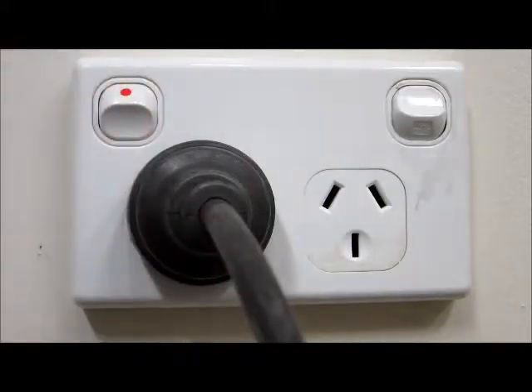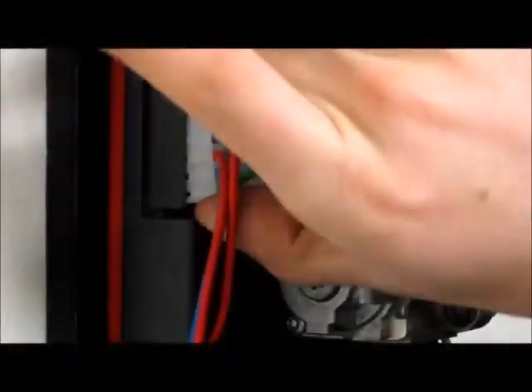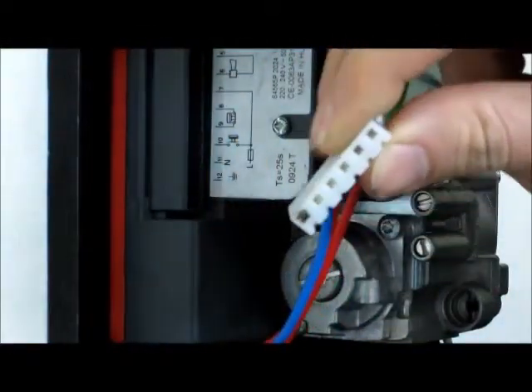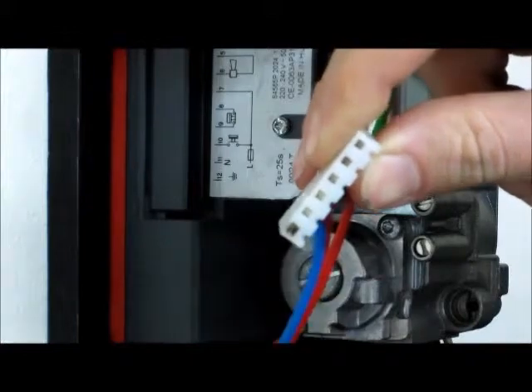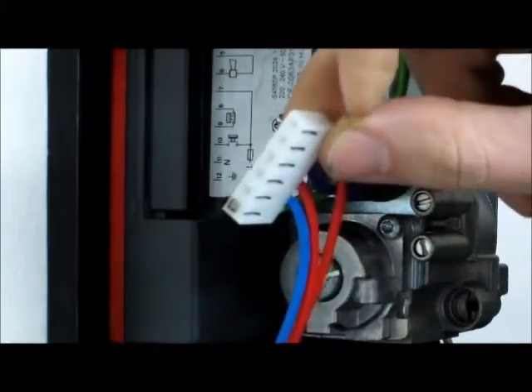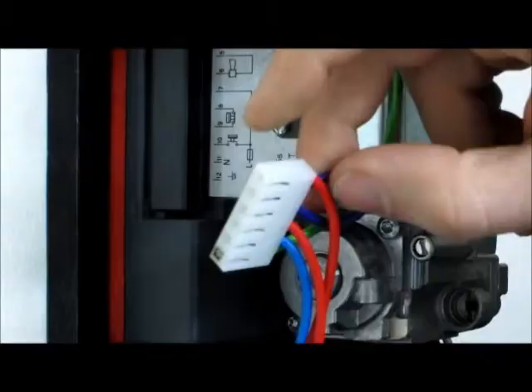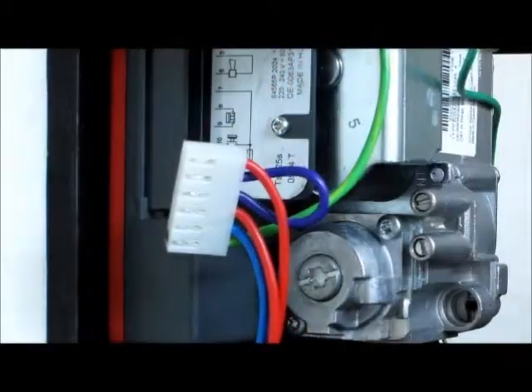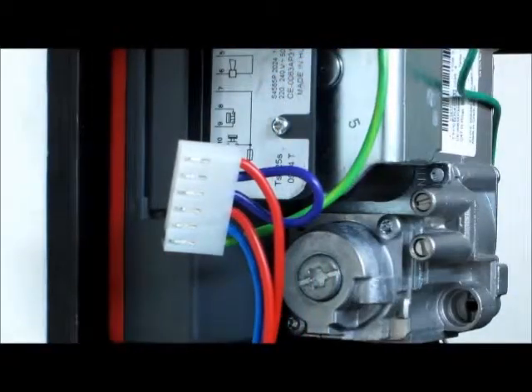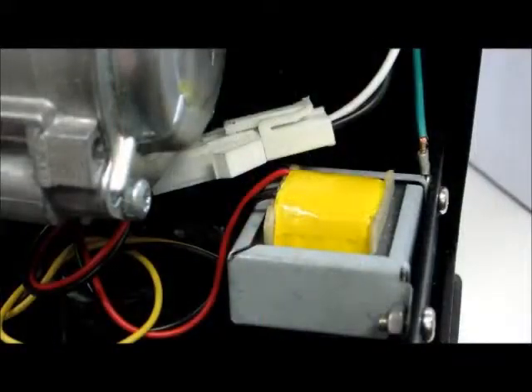Power up the unit, and if there is still no audible ignition signs, inspect the wiring harness plug for any signs of damage to the terminal pins or for any burning smells. If damage is located in the control box, your dealer should be contacted for replacement components. For US models, the transformer should also be inspected to verify that it is functioning correctly.